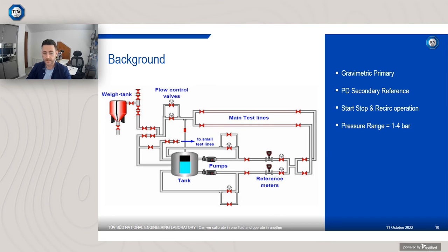Now the pressure is much lower. Historically, most calibration facilities for liquid operate at low pressure, because pressure wasn't deemed to be a significant influence on meter performance. We now know for certain flow meters it is, and if you are operating at high pressure, then you should ideally characterise your meter for pressure. But most liquid flow facilities are relatively low pressure, so we operate 1 to 4 bar. Temperature, again, fairly similar, 15 to 50 degrees Celsius.